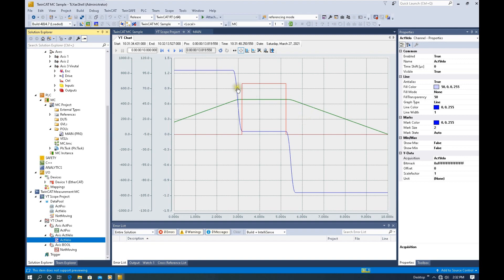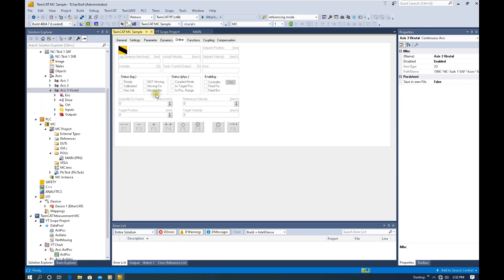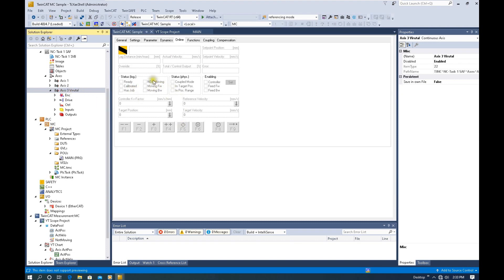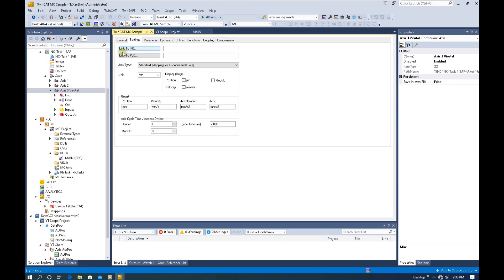We can use the trend or the commissioning panel here to monitor the actual position of the axis. In this test I will use a virtual axis. From the axis settings, we do not need to select anything — by default this axis will be a virtual axis. After we program the motion control command, we will connect the link to the PLC and connect that variable as an axis variable, so the motion control command will connect to this virtual axis.